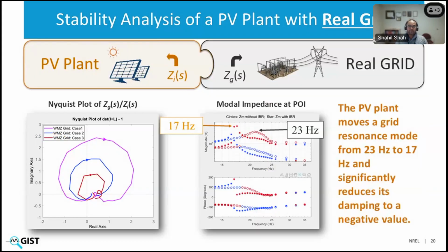To look at it from a different perspective, we can also look at what we call modal impedance response. So here the circles represent the modal impedance of the grid without this PV plant where we are doing this analysis, where we are connecting these two puzzle pieces. And when we connect the IBR to the grid, the modal impedance becomes this response that I'm showing through stars. And what it shows is that a grid resonance mode at 23 Hertz moves to 17 Hertz and it becomes unstable. So this particular PV plant is moving a 23 Hertz mode to 17 Hertz and it reduces its damping to a negative value.